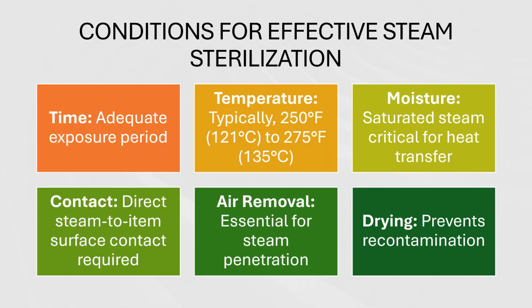The conditions. Effective steam sterilization, also known as high temperature sterilization, relies on several critical parameters. First is the time. This ensures microorganisms are exposed long enough to be destroyed. So remember our time. Usually it's a 4-minute phase or a 10-minute sterilization time phase. When we're talking about time, we're talking about the sterilization time. How long does it stay in that sterilization cycle?